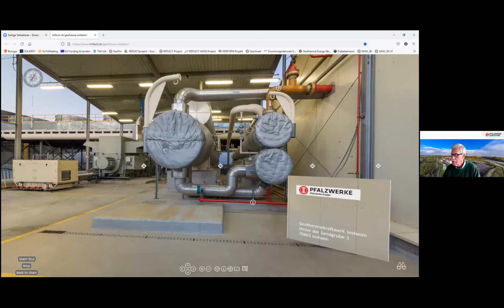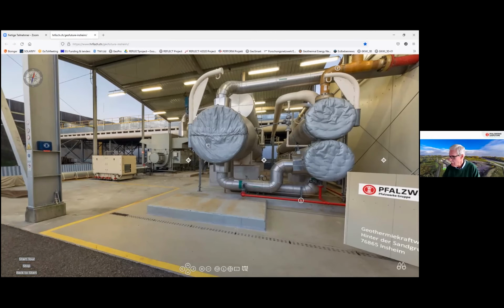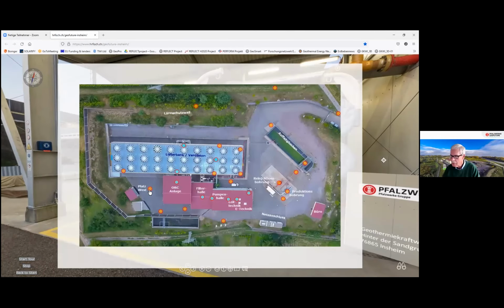And the working fluid in our ORC unit, this isopentane, is flowing through this line into the upper colder preheater. There we have the most scalings, and this is the coldest point of the heat exchanger system, and then flowing from this into the second lower, even warmer heat exchanger, and then entering at the bottom the vaporizer, where it will be fully vaporized. And from there, it will stream over as a vapor to our turbine, which we will see from the other side, where we have a better view.